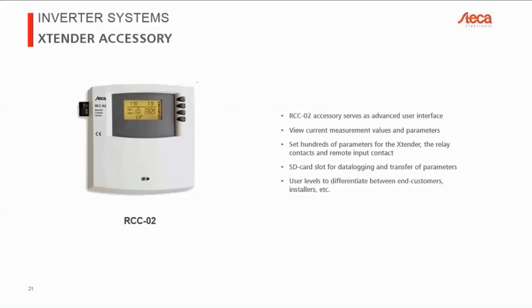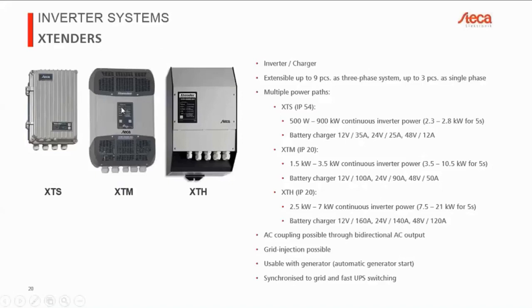For all of the Xtenders, we have an optional accessory, which is the RCC02. There's a special version of the RCC02, which is called the RCC03, which has exactly the same functionality. The only difference is it's made for integration into a wall. The RCC02 is basically a device which you screw onto the wall. The other one is a device which you slide into a wall to make it flush with the wall. So this serves, first of all, as a display for multiple devices. If I go back, you'll see that on the front, we don't have a liquid crystal display. We just have basically a group of LEDs, which are good for debugging and giving you a very rough state of service for the device. But of course, it doesn't give you any exact values on how much power you're using, etc.